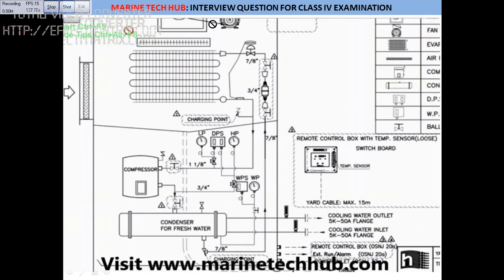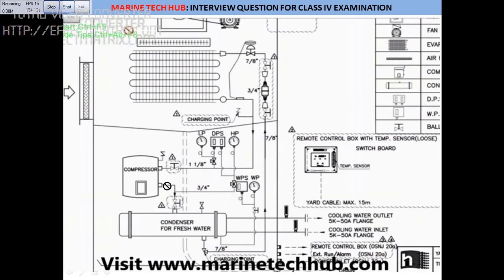If the belt is not okay and airflow is not adequate, heat transfer will not take place, and you can have ice formation in the evaporator — so checking the belt condition is very important. If everything is okay, the gas goes through the evaporator, then gets compressed in the compressor. The compressor has an inlet valve and an outlet valve. Always make sure you never close the outlet valve by mistake before starting the compressor, as that can damage it.